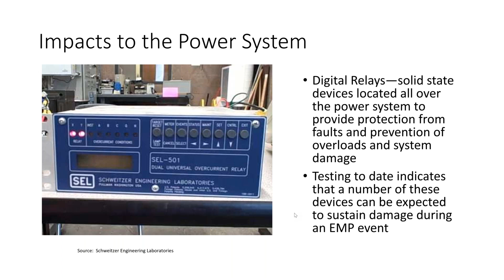The other issue here is relay misoperation, and the relay misoperation basically is caused by the same thing. And what I wanted to do here is basically separate the issue of damage. Now you can have the relays catastrophically fail, where they fail and they need to be replaced. We can also have a situation where the relay misoperates, and that is the signal from the sensing device into the relay can be changed by the EMP currents and flows that are in there to the point where the relay doesn't get damaged necessarily, but the relay will misoperate. It will either trip devices that shouldn't be tripped or miss fault currents that should be picked up and cause the system to be taken out of service. So this is the situation where if enough of this occurs, then you could trigger a wide-scale electrical outage on the system.